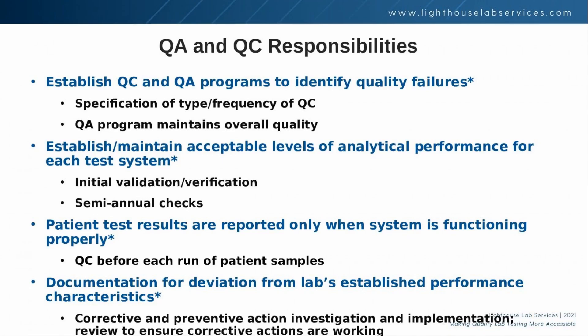Finally, in instances where there is a quality failure, the lab director will initiate corrective and preventive action processes. This involves, first, the identification of the root cause of failure; secondly, a plan for correcting the failure and any necessary actions that need to take place; and finally, a way to assess if the actions implemented actually prevented the failure from happening again.